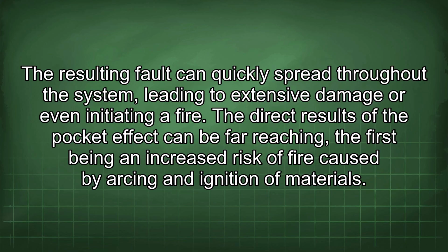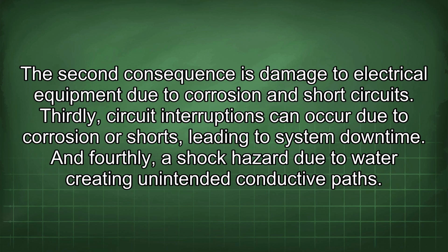The direct results of the pocket effect can be far-reaching, the first being an increased risk of fire caused by arcing and ignition of materials. The second consequence is damage to electrical equipment due to corrosion and short circuits. Thirdly, circuit interruptions can occur due to corrosion or shorts, leading to system downtime. And fourthly, a shock hazard due to water creating unintended conductive paths.